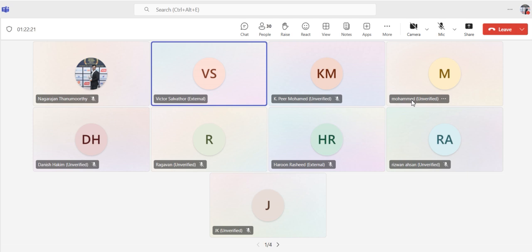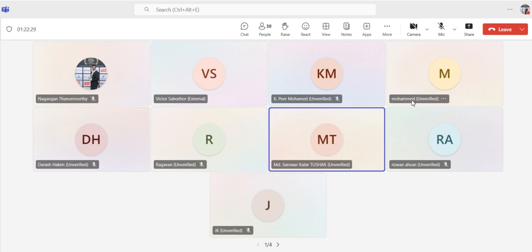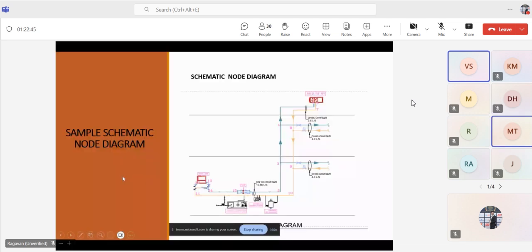Any other question? Hello, sir. Yes. The chart you showed here for equivalent length for valves, could you please share that? Here you can see that flexible connection is missing. So how much equivalent length should be considered for flexible connection? The flexible connection is very minimum, actually. It's not like other fittings. So here you will not find it, but if there is no chart value, there is a default value of 0.3 to 0.5 meter you can consider. That's the maximum value.